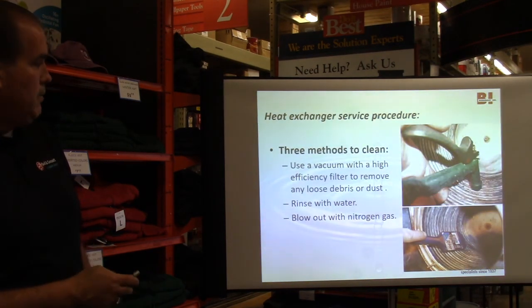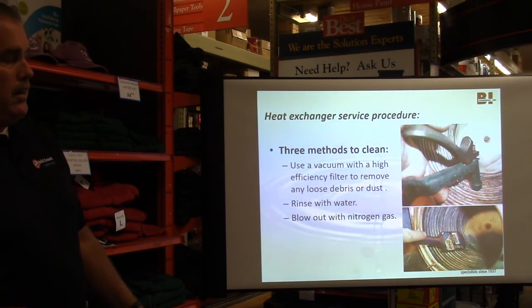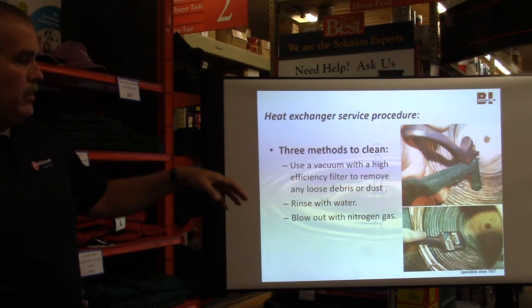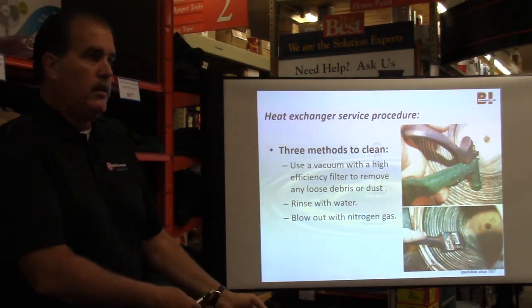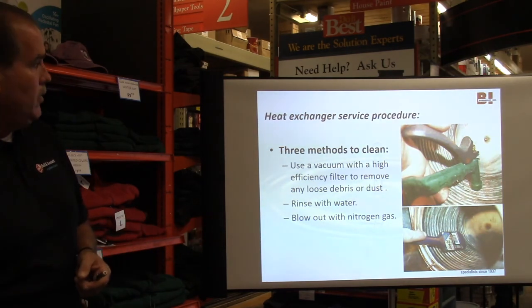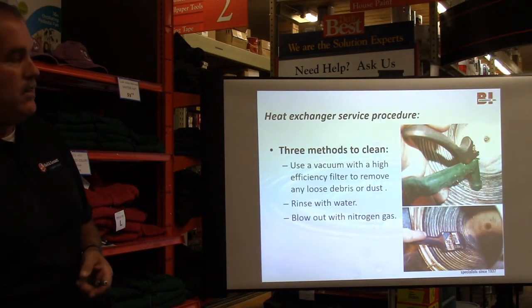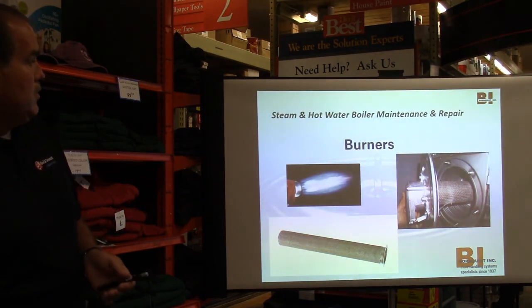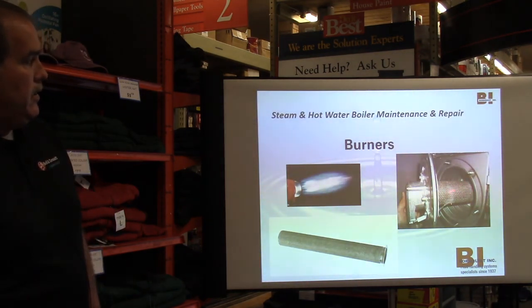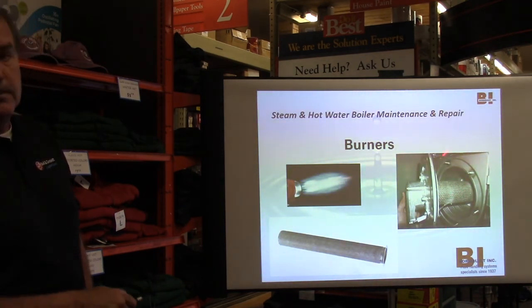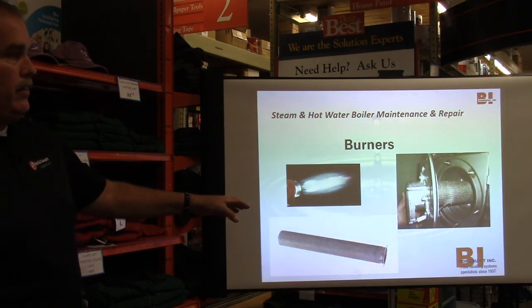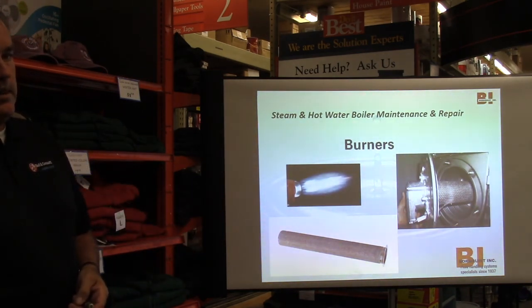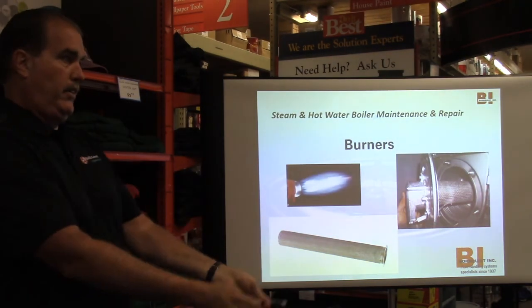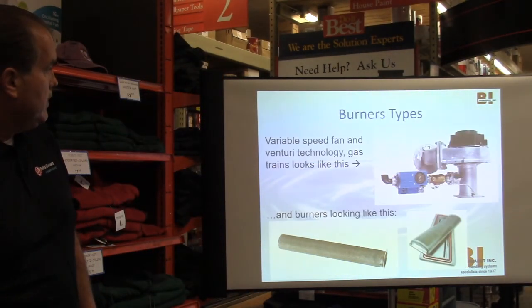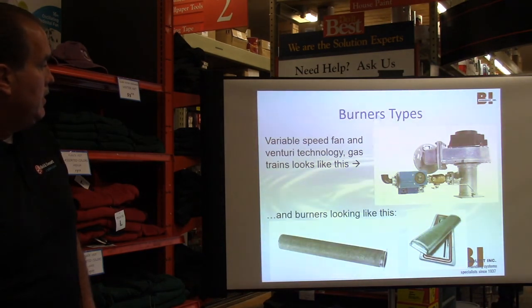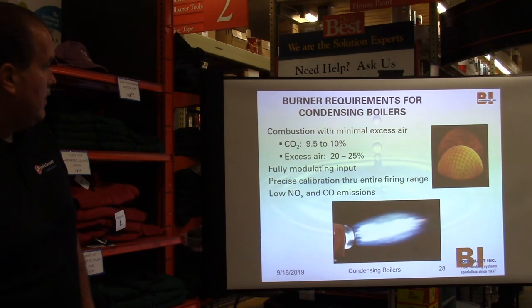Here I was saying, typically on the smaller one, they'll brush and rinse with water. On a higher efficiency boiler, there's usually a condensate drain, so it's going to drain out the water. On an atmospheric, you cannot do it this way. You have to just use probably nitrogen and a brush. This is what I'm talking about when you can pull the burner. The heat exchanger is what's around it. But this is more of a higher efficiency type piece of equipment rather than your cast iron, flame underneath, where you can see the flames. Different burner assemblies, but these are more your modulating type.